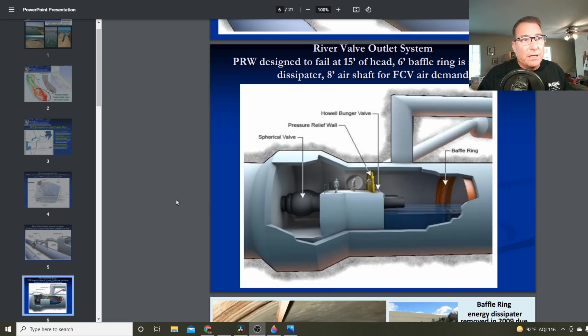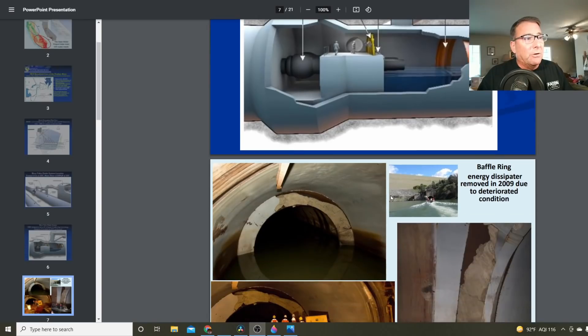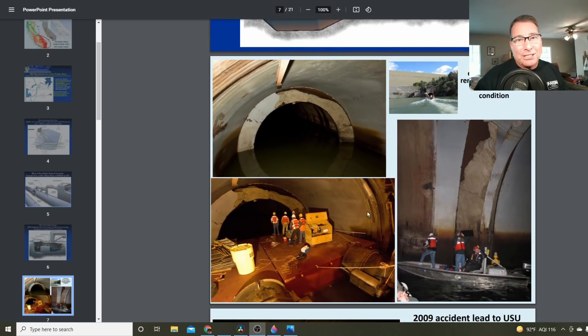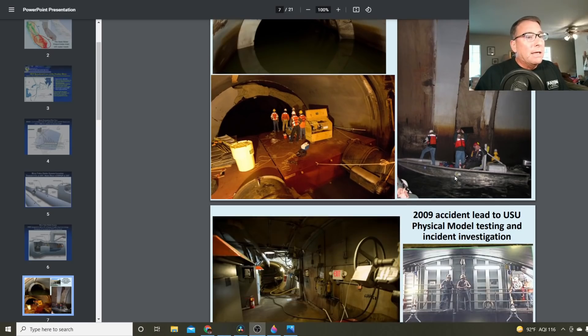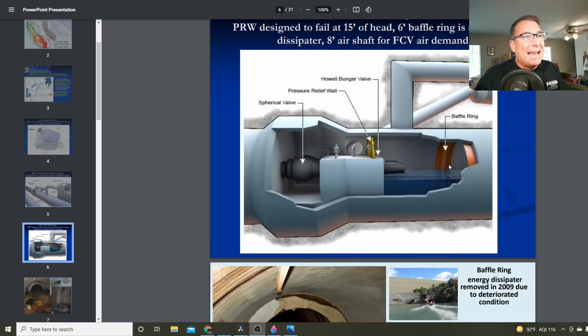Here's the original design of the river valve outlet system that caused so many troubles. There's a spherical valve, another valve, a baffle ring to slow down the water and absorb energy, and then a pressure relief wall. Crews were required to come down here to operate the system. Over the years, the baffle ring began to deteriorate, so they took it out — but then made the fateful decision to run the river valve outlet system without the baffle ring. The energy from the water ejecting through the valves was no longer dissipated, creating such strong back pressure that it blew out the pressure relief wall and nearly took out the employees sent down there to open the valves.